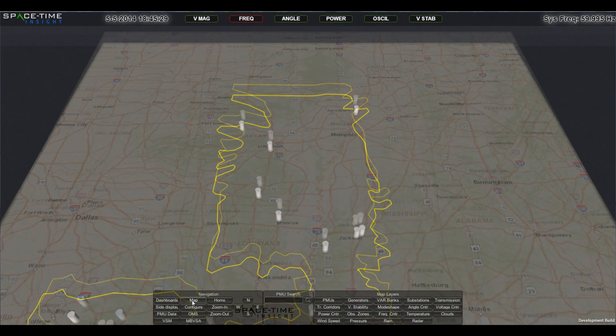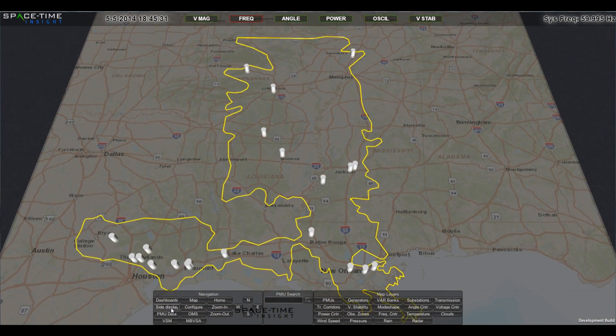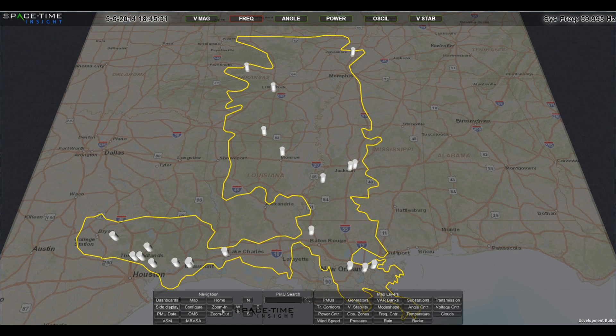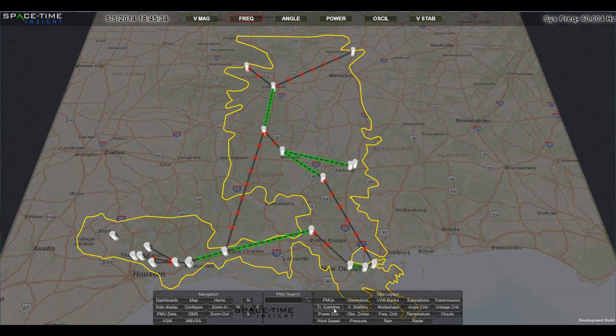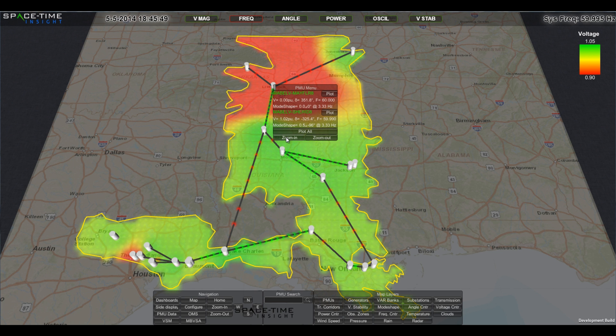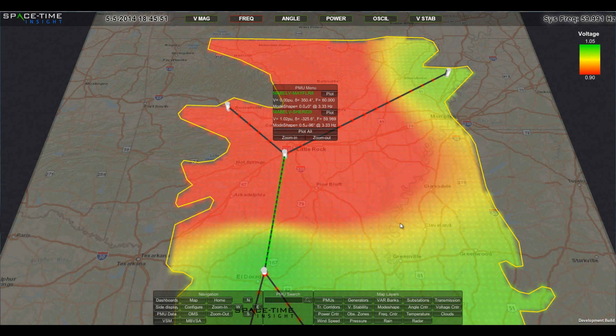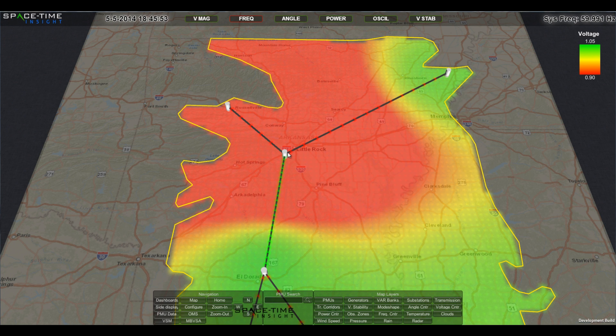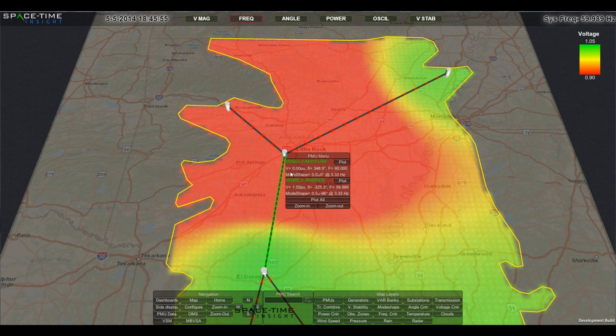Returning to the 3D map, major transmission paths based on system topology and load flow models are displayed with a phase angle difference along a transmission path. Phase angle differences provide an excellent measure of the level of stress on that part of the grid. This reveals a considerable amount of power being transmitted along the grid, resulting in high levels of system stress.